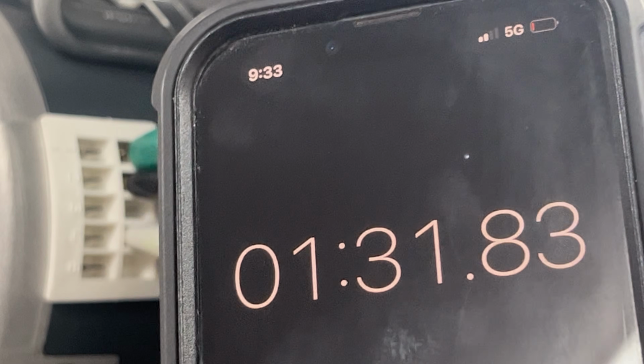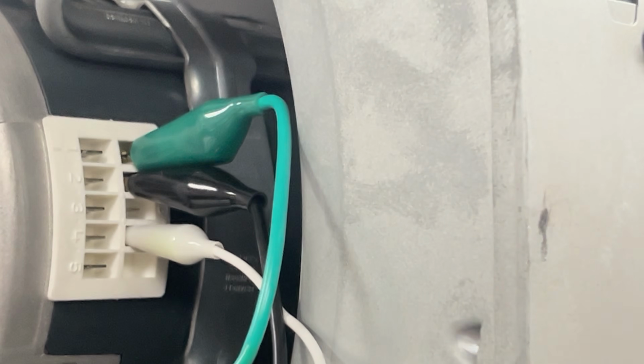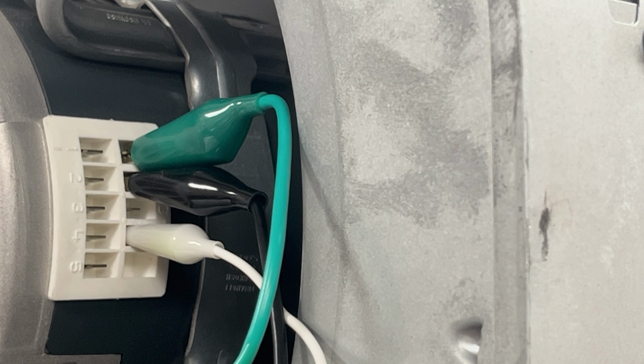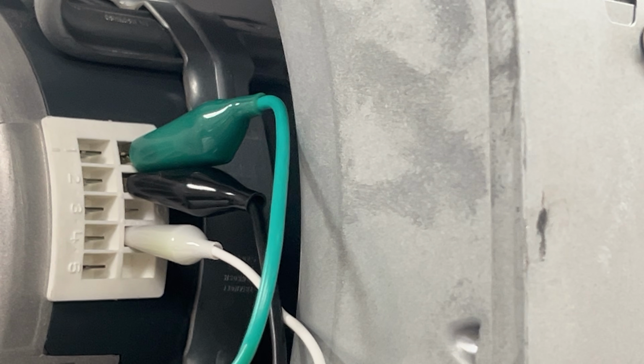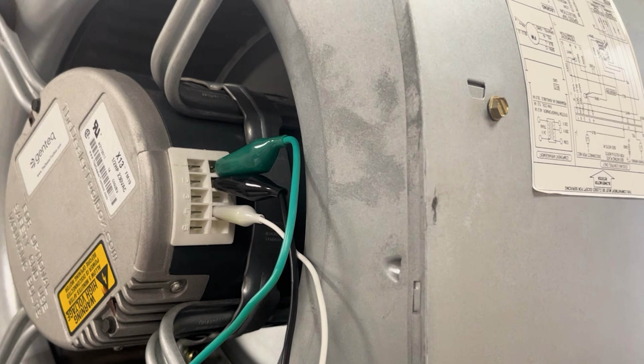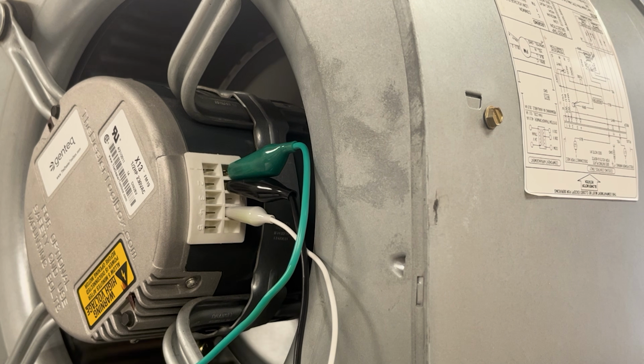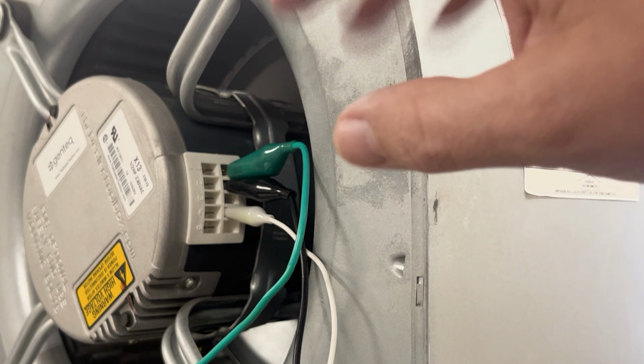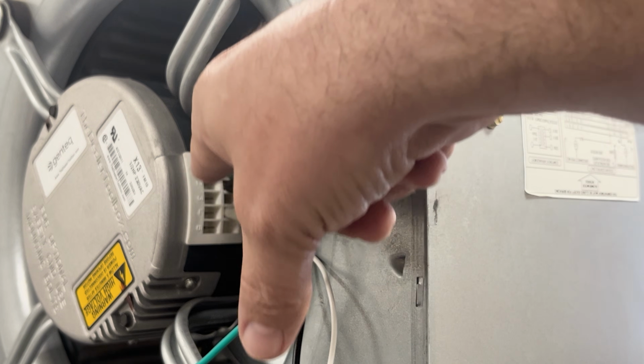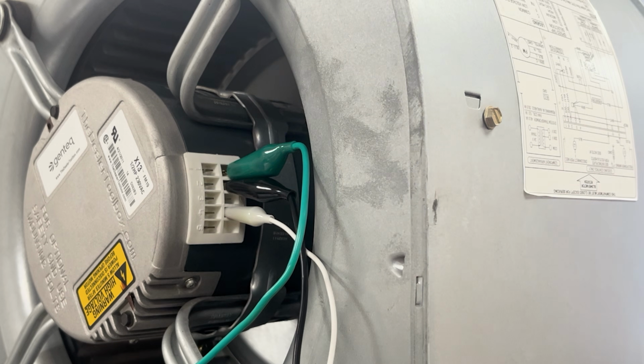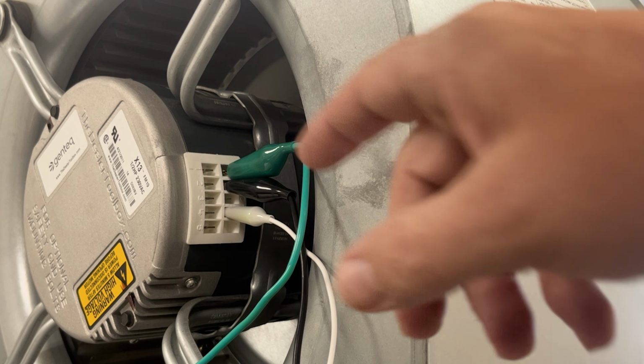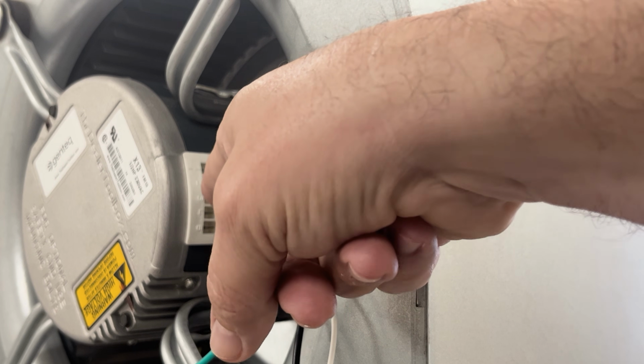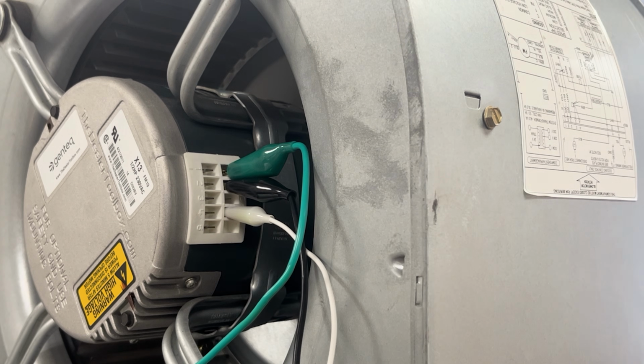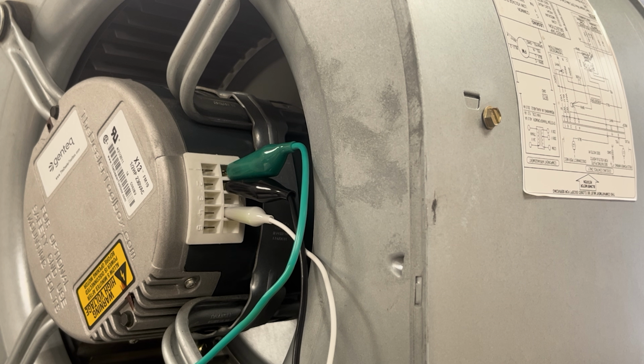And so there you go, it's very consistent. So if we had a motor that we thought was going bad, then what we would do is we would first put the 240 on it, make sure it has 240 volts. So we're going to check power between L and N. There should always be 230 volts there. And then I'm going to apply 24 volts to 1, 2, 3, 4, and 5 to see if I can get that motor to engage. If I can get that motor to engage, then you do not have a bad motor.